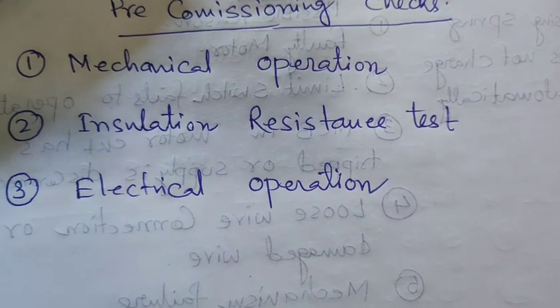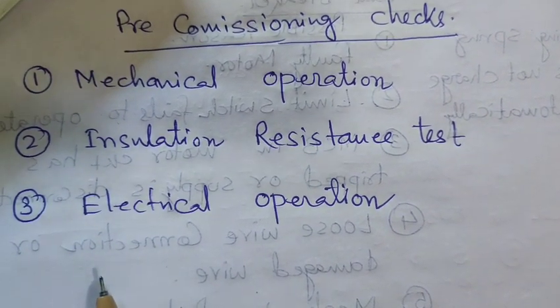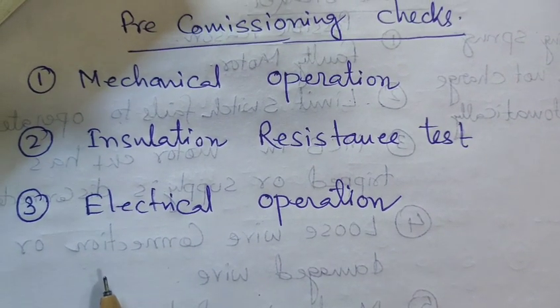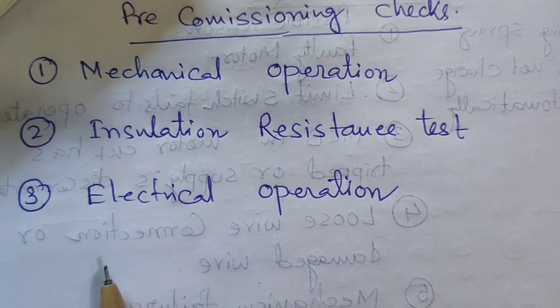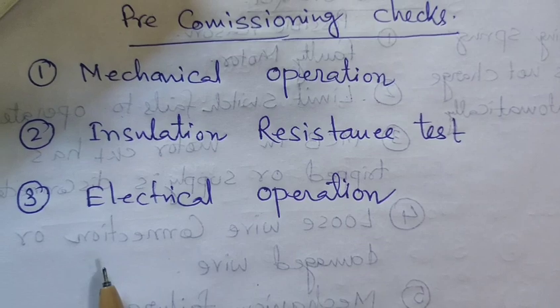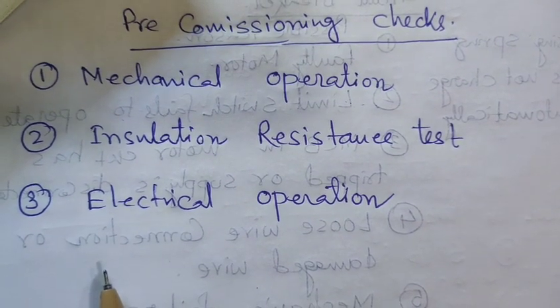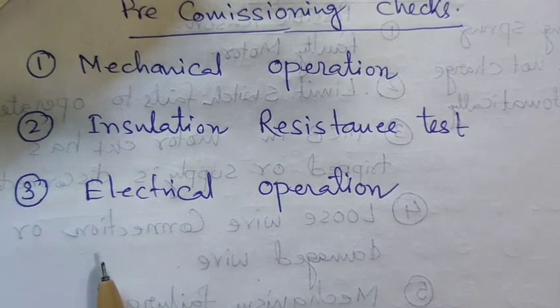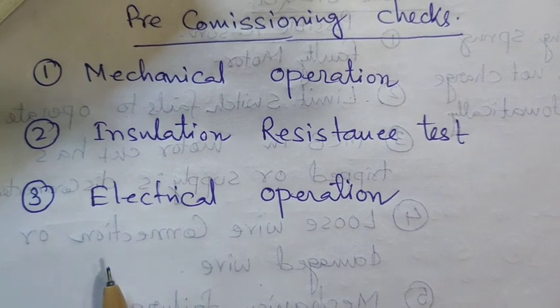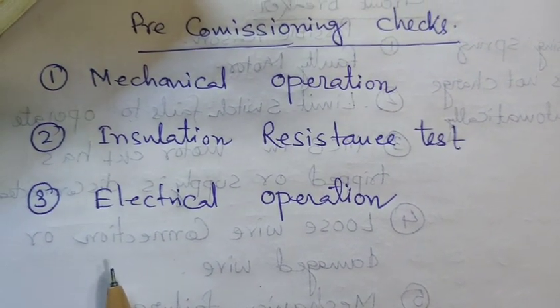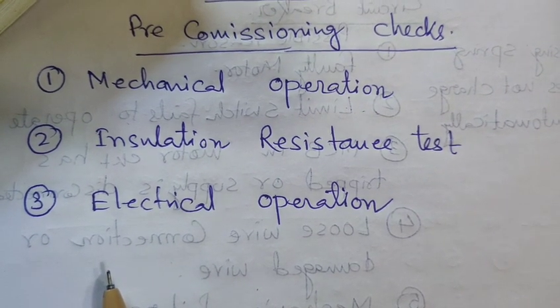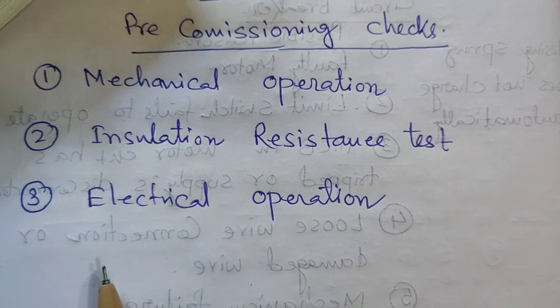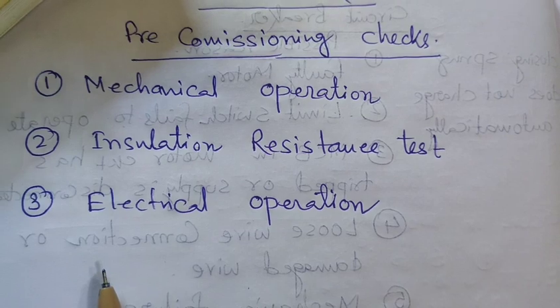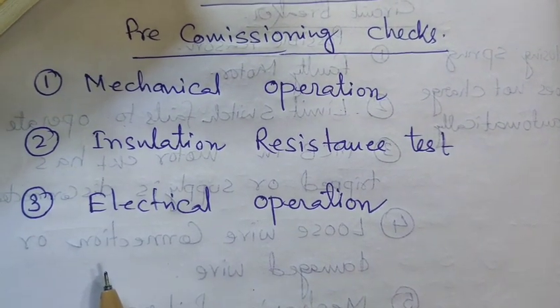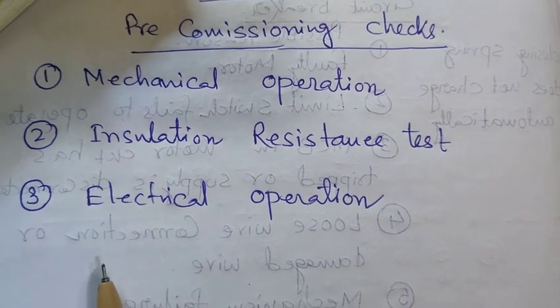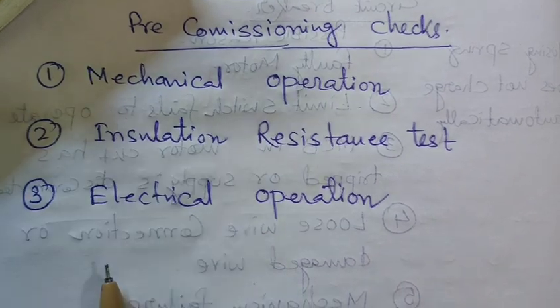Electrical operations, this is the third and the last operation. So what type of electrical operation do you have to check? You will get a schematic diagram of the circuit breaker from the manufacturers. You have to thoroughly check that all the connections, parameters and equipment inside the circuit breaker are as per the schematic diagram. With the help of the multimeter you have to check the continuity of all the parts, and first you have to tighten all the terminals and connections of the spring charging motor, tripping coil, closing coil, all the terminals of the CT, all the terminals of the control panel wiring, and all the connections of the 4 square cables for the AC supply and DC supply.